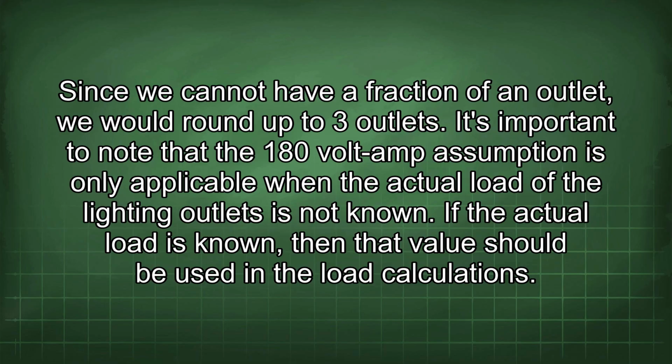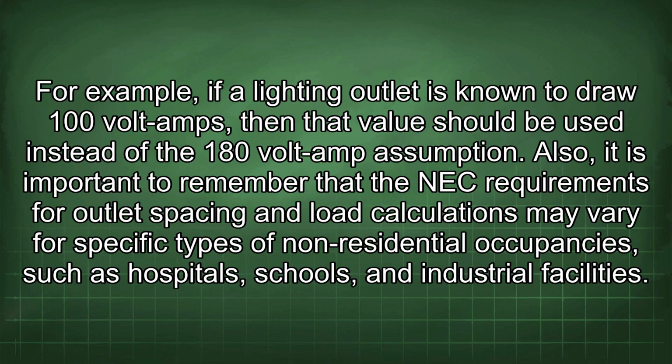It's important to note that the 180 volt amp assumption is only applicable when the actual load of the lighting outlets is not known. If the actual load is known, then that value should be used in the load calculations. For example, if a lighting outlet is known to draw 100 volt amps, then that value should be used instead of the 180 volt amp assumption.